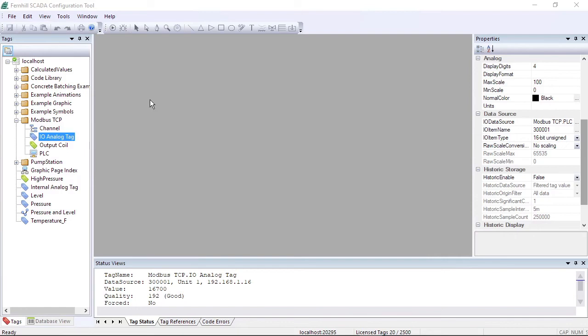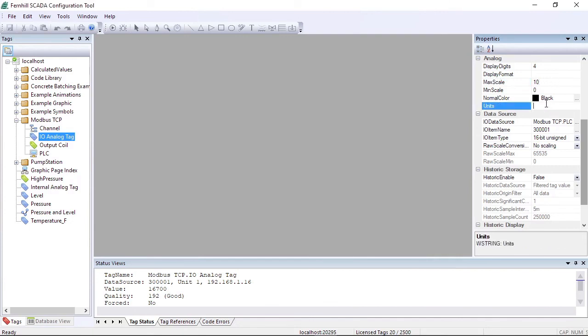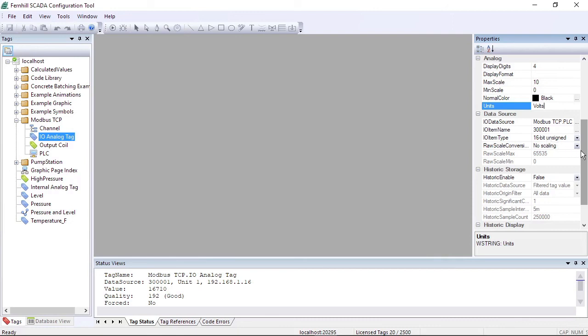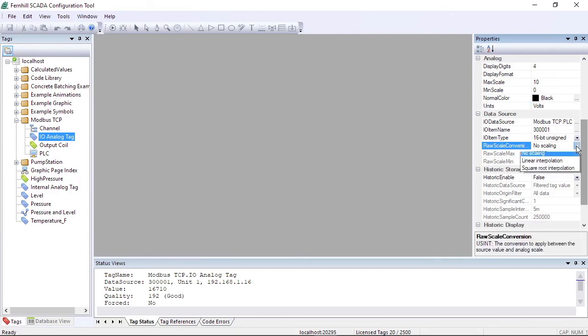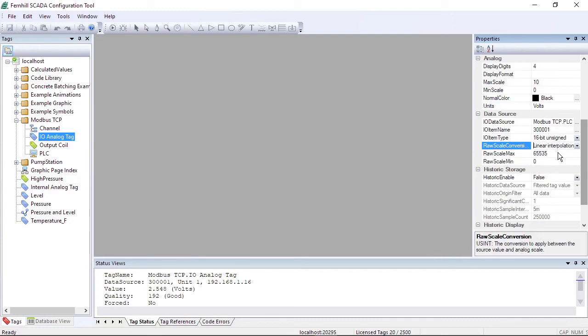To do this, we set the max scale to 10. In the units field we enter volts. For the IO item type field we keep the value of 16-bit unsigned, which interprets the word register as a 16-bit unsigned quantity. We change raw scale conversion to linear interpolation and set the raw scale max to 65,535.